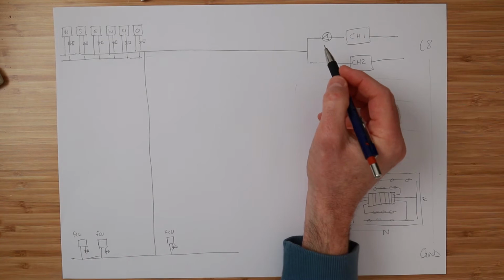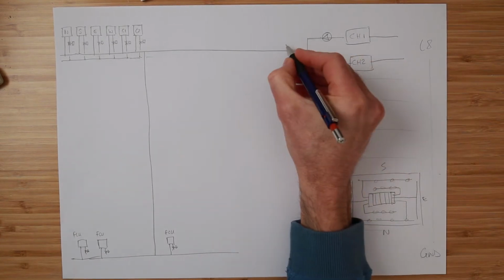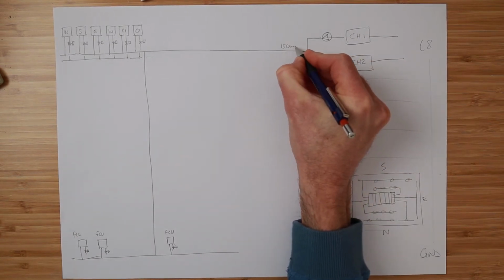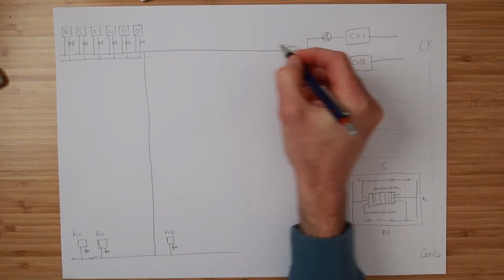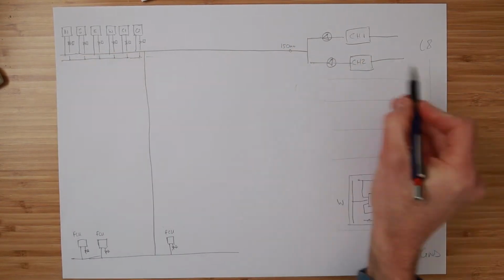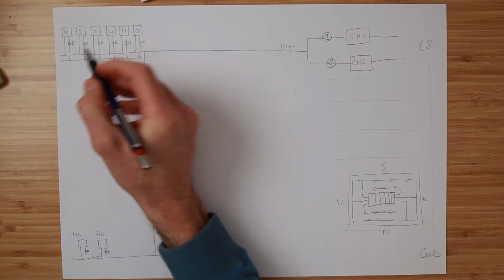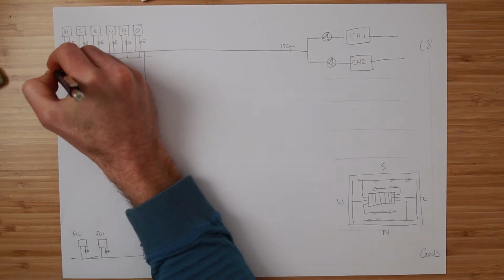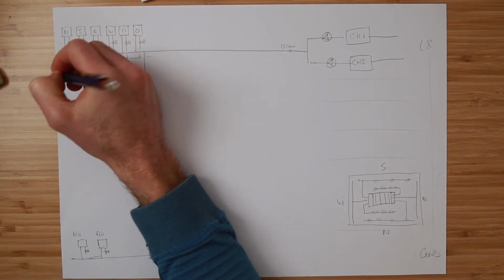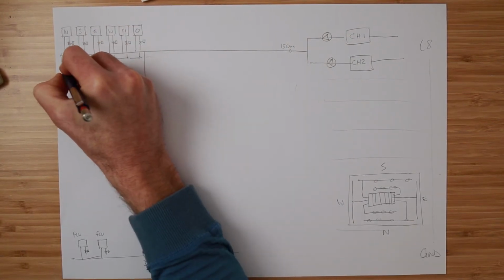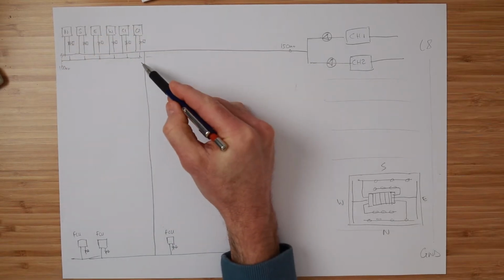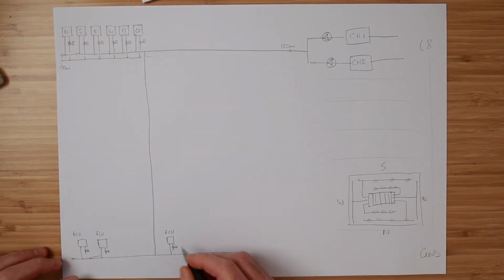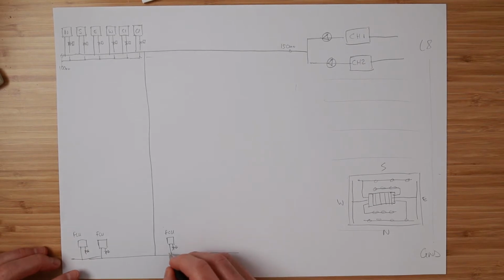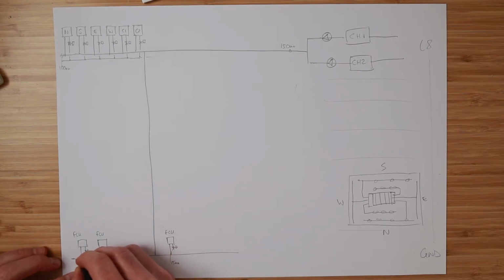So let's say, for example, this pipework was about 150 millimeters. And then perhaps, down here on the same level in the plant room at the last air handling unit, maybe the pipework was a little bit less, so it'd be 100 millimeters. And then, there's not much cooling demand down here. So down here on our fan coil units, the fan coil unit's probably only 15 millimeters. The fan coil unit pipe.